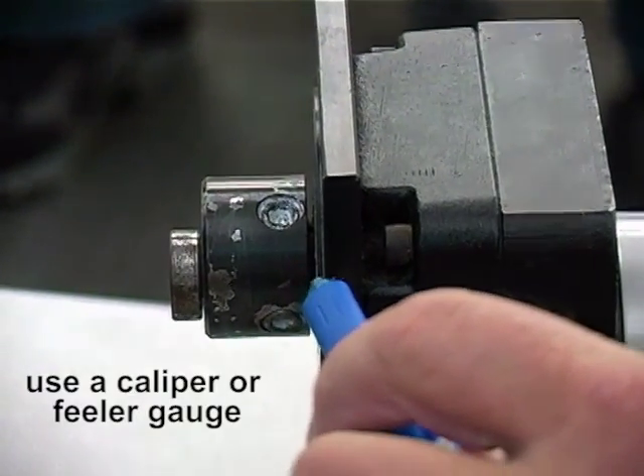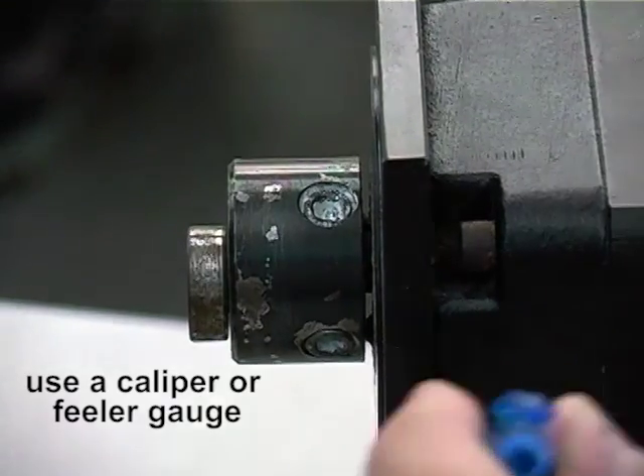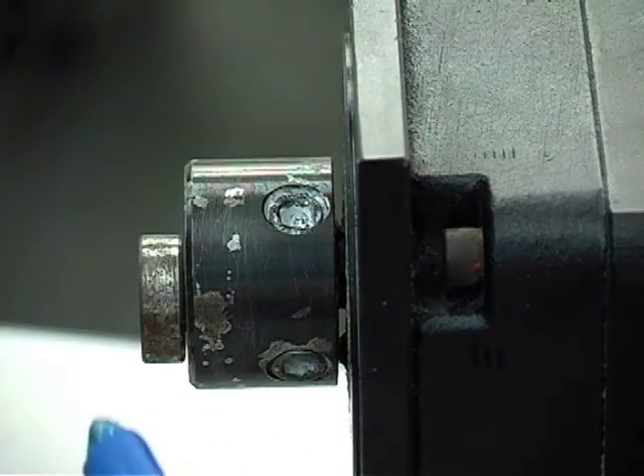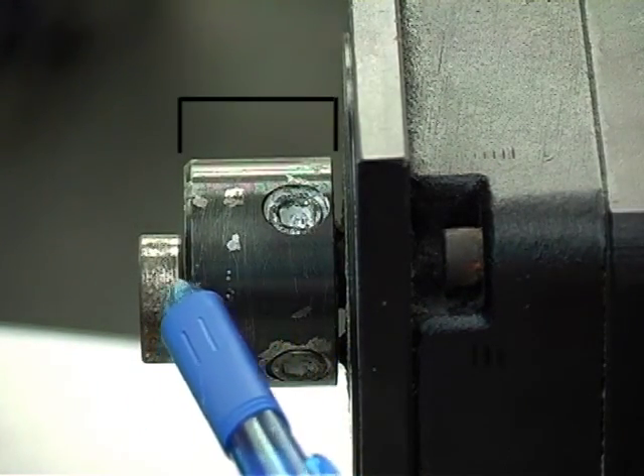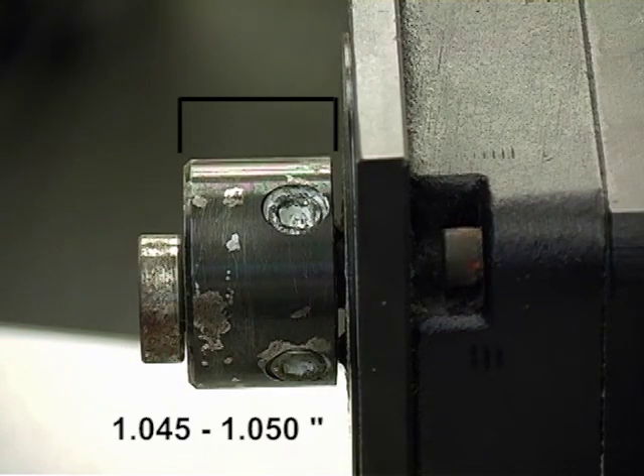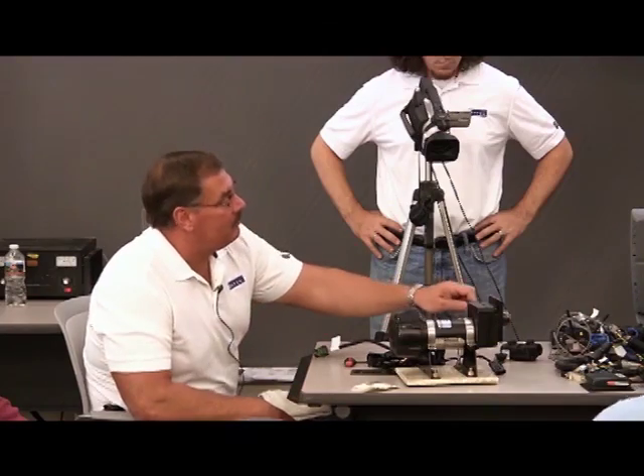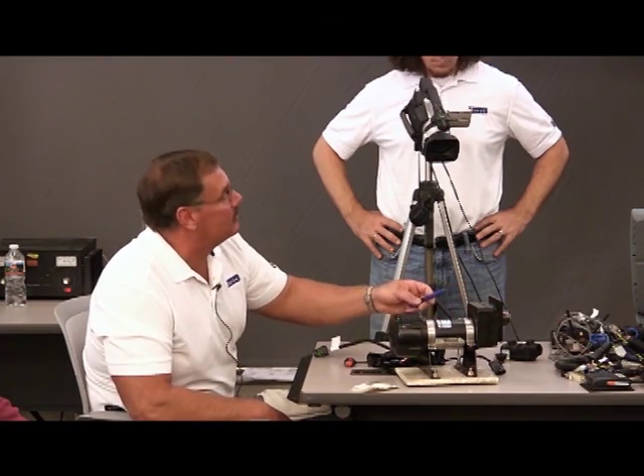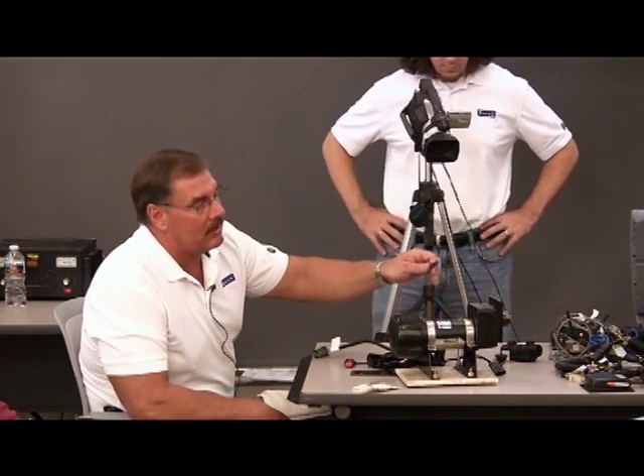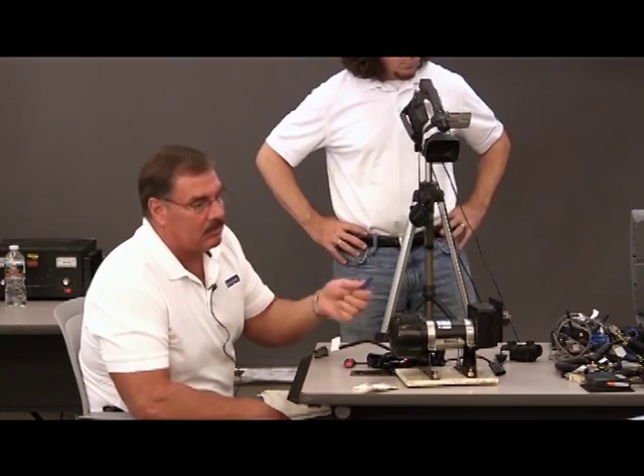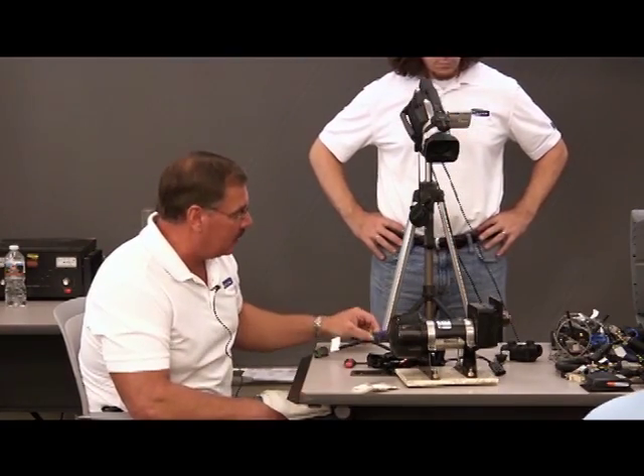Either use calipers or a feeler gauge before you take the one out. From the facing of the plate of the motor to the front of this collar, not the bearing, we want that to be within a range of 1.045 to 1.050 inches. Obviously, if we get it too close, it's going to bind and not run smoothly. If we get it much more out, it'll still run, but you're going to hear it knock and make a lot of noise.